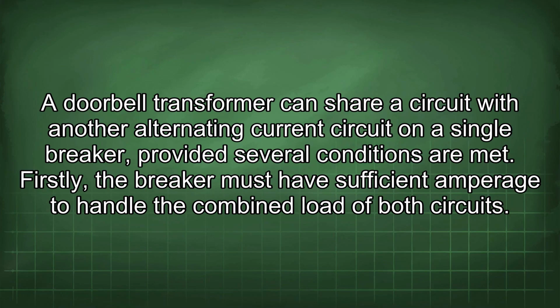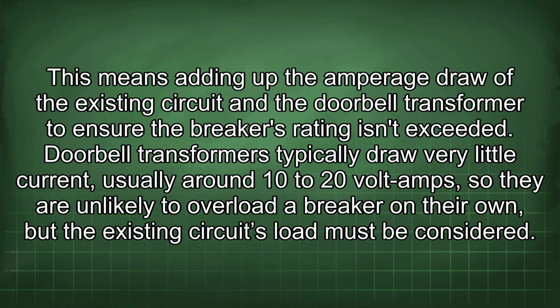A doorbell transformer can share a circuit with another alternating current circuit on a single breaker, provided several conditions are met. Firstly, the breaker must have sufficient amperage to handle the combined load of both circuits. This means adding up the amperage draw of the existing circuit and the doorbell transformer to ensure the breaker's rating isn't exceeded. Doorbell transformers typically draw very little current, usually around 10 to 20 volt amps, so they are unlikely to overload a breaker on their own, but the existing circuit's load must be considered.